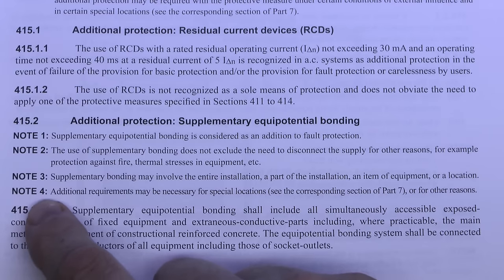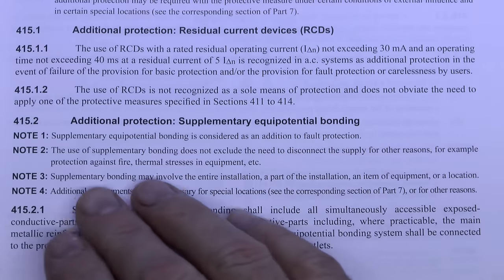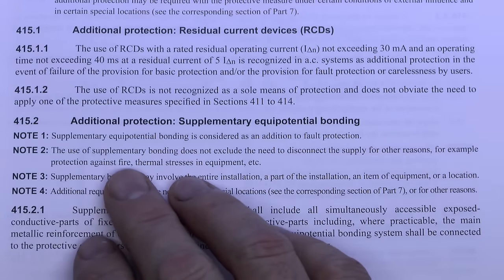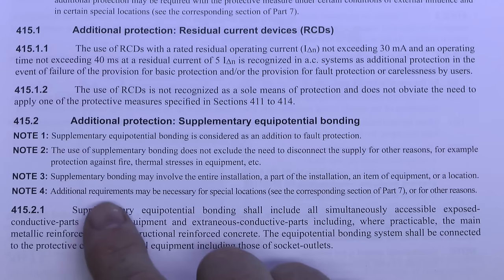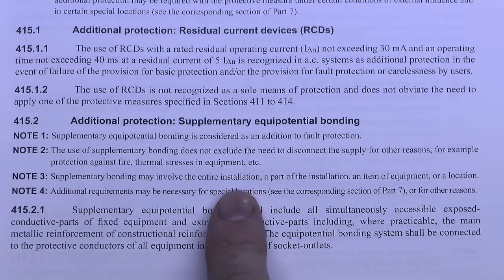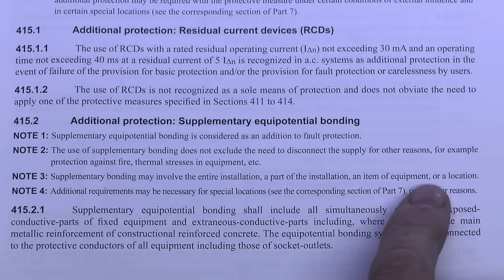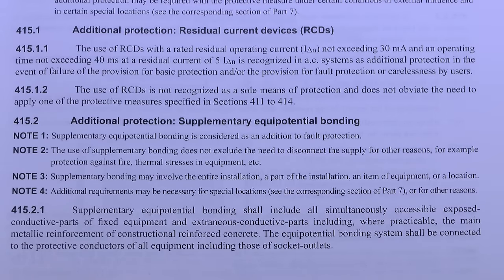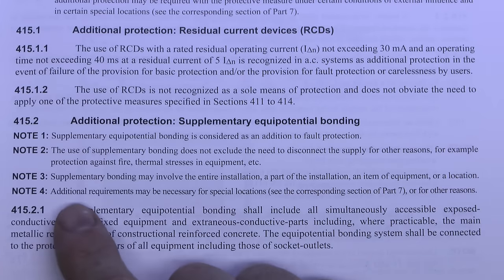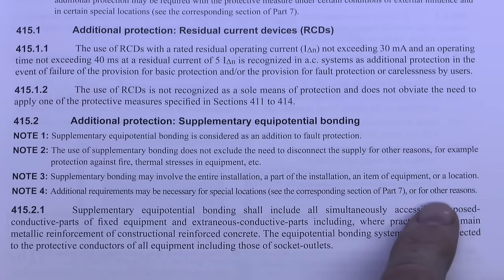Supplementary Equipotential Bonding is considered as an addition to fault protection. The use of supplementary bonding does not exclude the need to disconnect the supply for other reasons, such as protection against fire, thermal stresses in equipment. Supplementary bonding may involve the entire installation — as covered in the previous episode — or a part of the installation, an item of equipment, or a location such as a bathroom. Additional requirements may be necessary for special locations; see the corresponding section of Part 7.